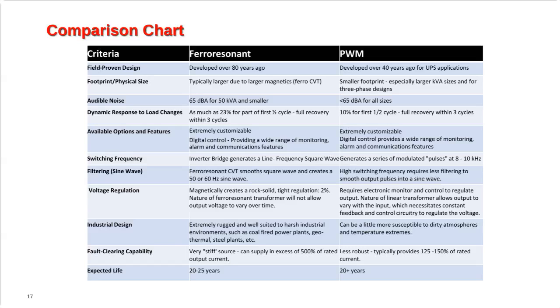Audible noise is relatively similar for both models. The switching frequency of the Ferroresonant transformer is 50 hertz, so it creates a low frequency buzzing noise. With PWM, because its switching frequency is 8 kilohertz, it's a high pitch noise that you hear. So they're two very distinct noises, but they are in some respects at the same dBA level. Dynamic response to load changes for the Ferroresonant is not as good. It can be up to 23% for the first half cycle, but then we say it will recover quickly within 3 cycles. For PWM, it's 10% for the first half cycle and then full recovery within 3 cycles.